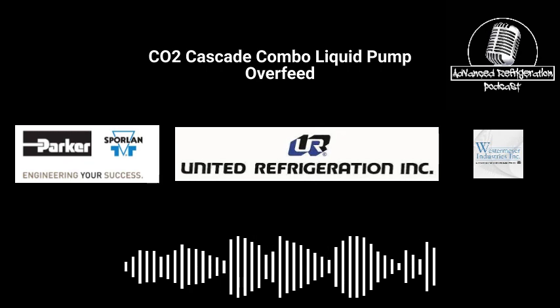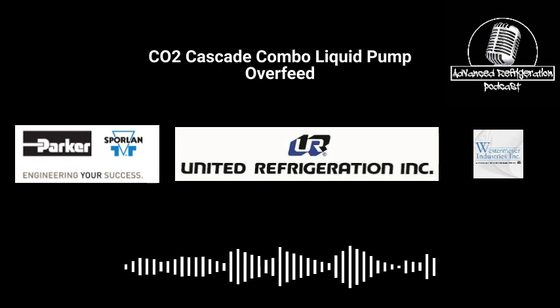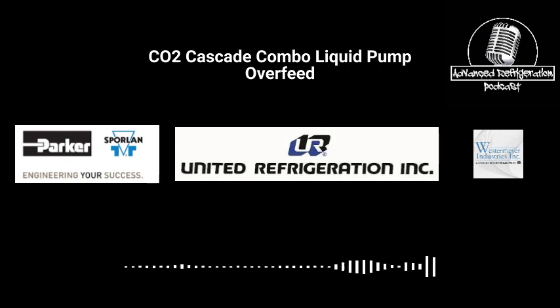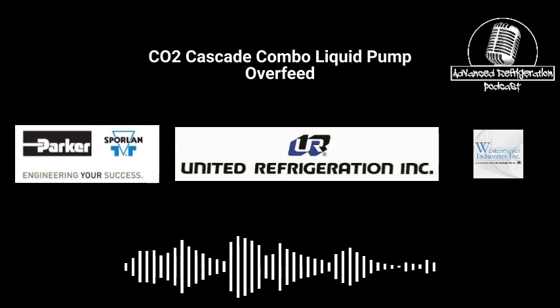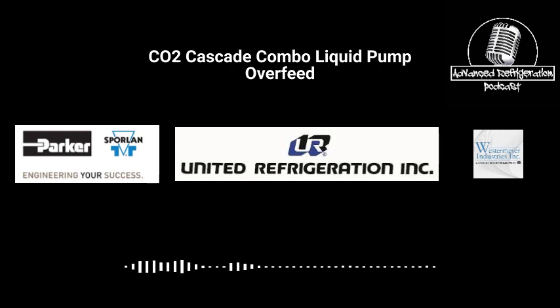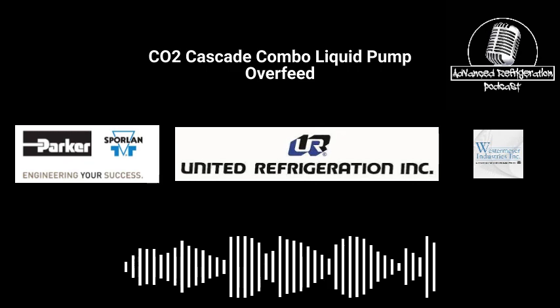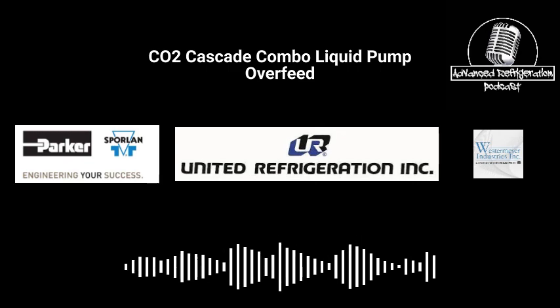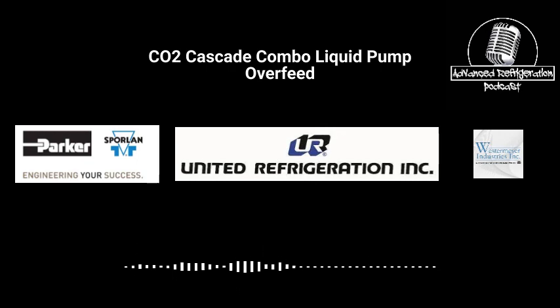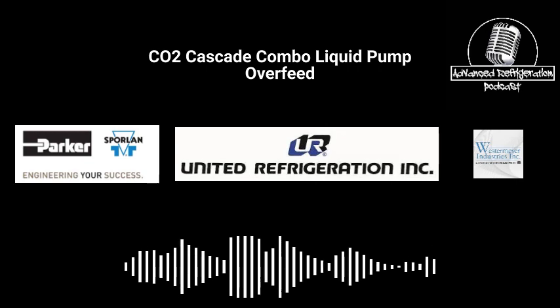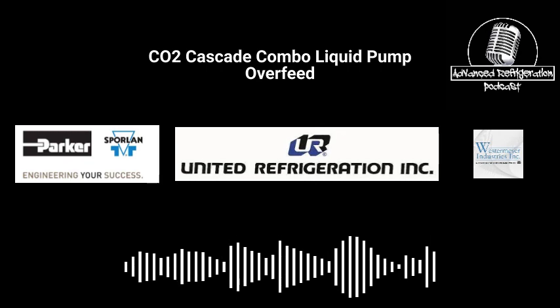I mean, that's a way better setup, I think, than what they run in the low temp. Just for the fact that compression ratios are going to be ridiculously low on both ends, the HFO and the CO2. The other benefit is, like, all the Walmarts right now, we have all these problems. These stores are like 8-9 years old now. Get to 10 years, all the Armaflex is shot because it has -20 degree CO2 floating around the entire store. So any little crack in the Armaflex instantly starts to grow ice. So it becomes this nightmare.